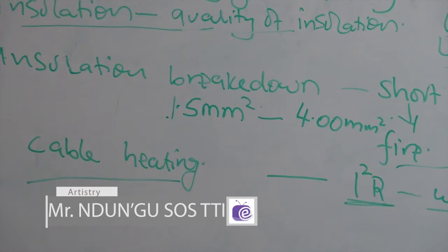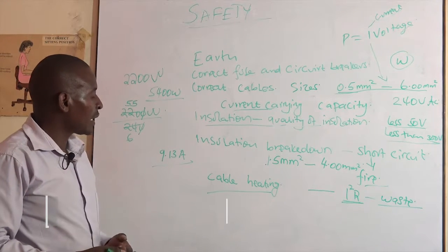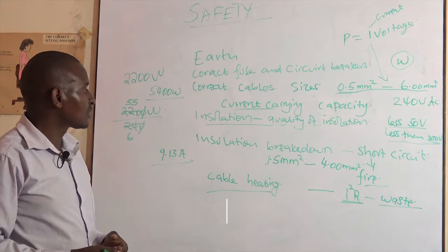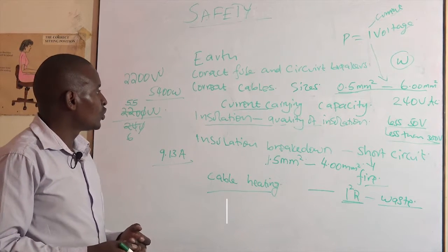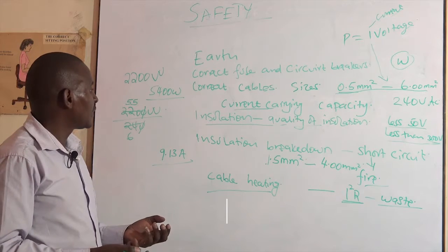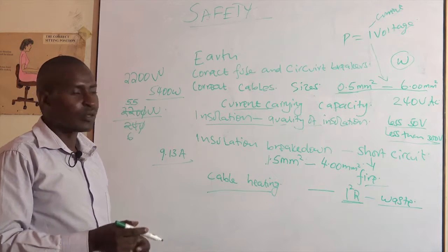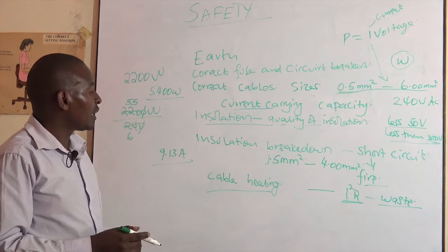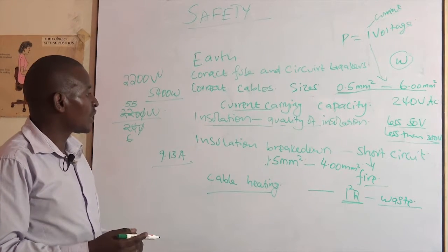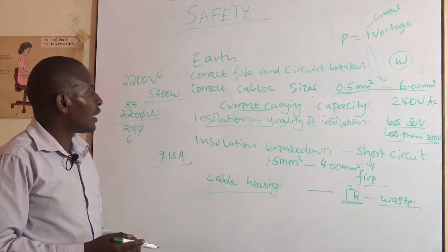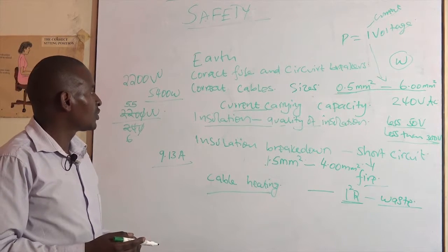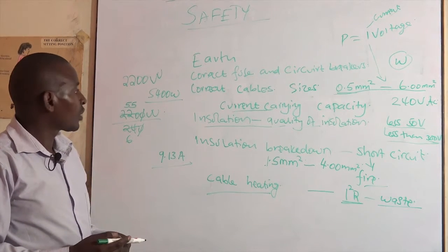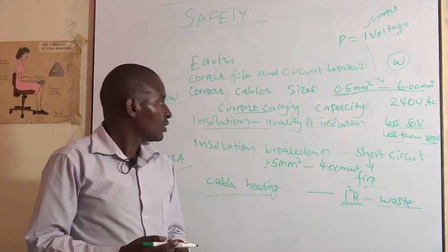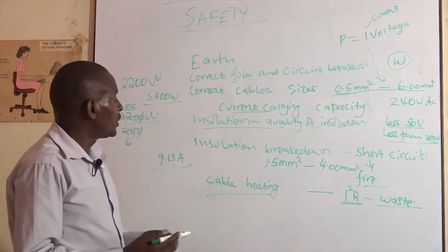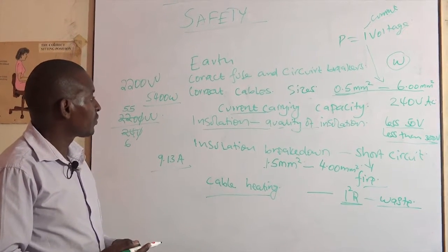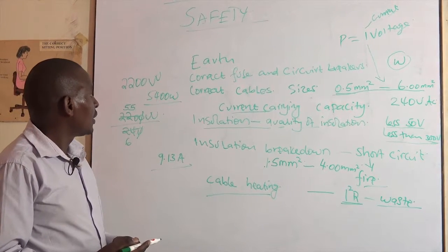Sometimes, even if you are in a complete installation where all the final sub-circuits have been fixed and you want to put an additional load, it is always good that instead of adding on the installation that is already there, you make a different circuit so that you are able to feed the load that you want without any problem. And that will of course be more safe.